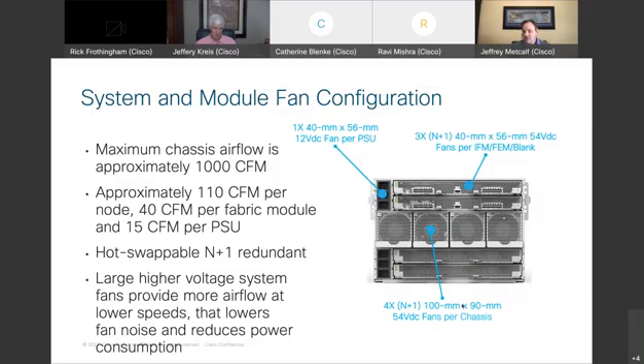Are you familiar with fan affinity laws? I'm certain there's not many, but power consumption is not directly proportional to fan speed. It's actually a cube rate. So when you increase the fan speed, it's a cube of that proportional response. For example, these fans at idle can be consuming 3 watts, but if you move it to 50%, just a 50% increase, it's not a 3 watt increase in power. The fans increase to almost 60 watts each. So it's a cube rate of that response.